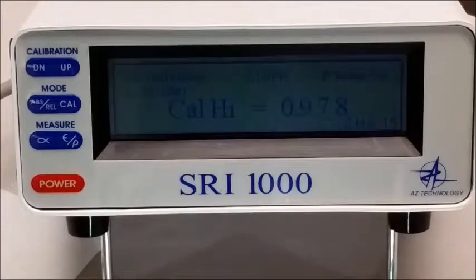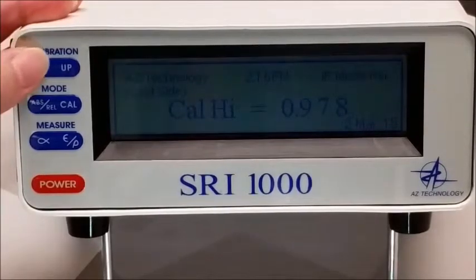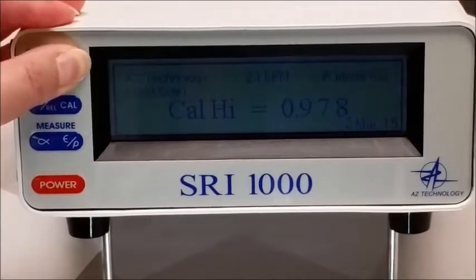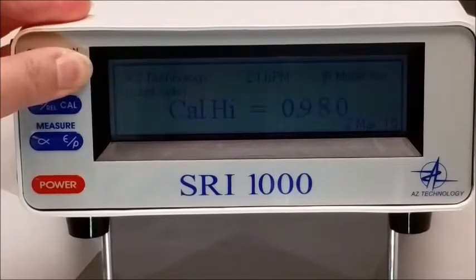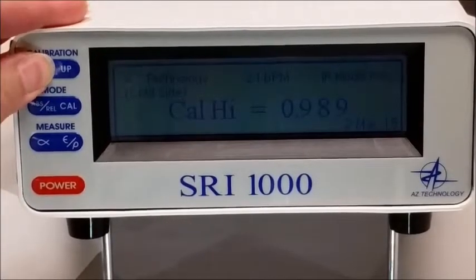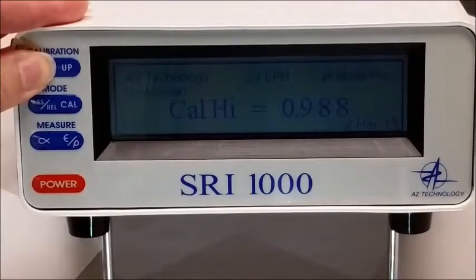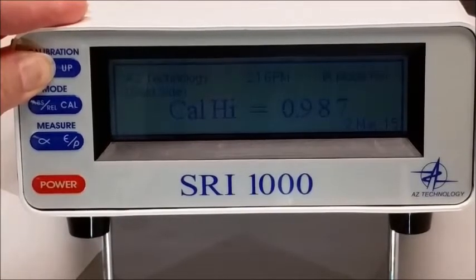If this value does not match the RTH value on the calibration sample label, the value can be changed up or down. Changing the value is done by simply pressing the up or down on the calibration key. A long press release moves the second digit. A short press release moves the third digit. Once the value for Cal high is acceptable, press the Cal button a second time.